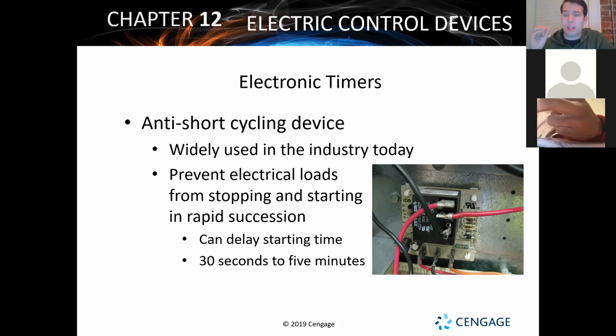It makes the contactor sound like a machine gun. It goes clack, clack, clack, clack, clack. It's just constantly going in and out really, really quickly, and that's extremely bad for the system. Even if it's not doing that level of short cycling, if it's just constantly having to come on, shut off, come on, shut off, come on, shut off.